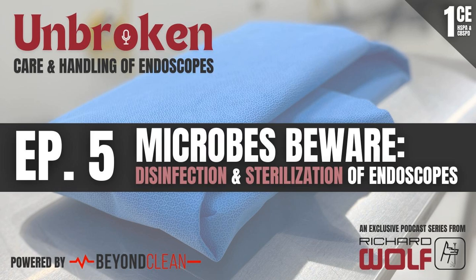Yeah, of course. So we have endoscopy that's being done right in our SPD OR spaces. And then we have that endoscopy that's being done all the way in the family health center. And they each have different storage and modalities, things of that nature. And when you're in a closed space, my best experience has been in a system that isn't a large red bin, that is segregated away, that's by itself when it's coming to you to keep it from damage. Then when you're sterilizing it, having that container system to place the scope in will prevent damage. I've seen facilities that are just wrapping scopes by themselves and there's no container. You want to make sure that you have a nice solid container that's going to keep that scope safe, stable, and segregated away. And then if it's wrapped, you're going to wrap it and sterilize it. Same if it's a container system. My ASCs were space restricted, so we went with wrapping everything.